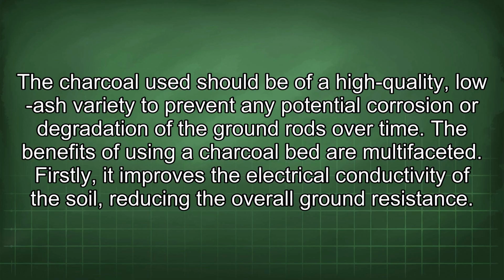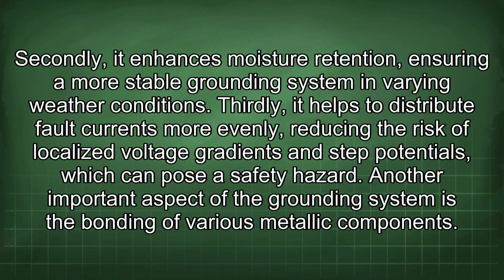The benefits of using a charcoal bed are multifaceted. Firstly, it improves the electrical conductivity of the soil, reducing the overall ground resistance. Secondly, it enhances moisture retention, ensuring a more stable grounding system in varying weather conditions. Thirdly, it helps to distribute fault currents more evenly, reducing the risk of localized voltage gradients and step potentials, which can pose a safety hazard.